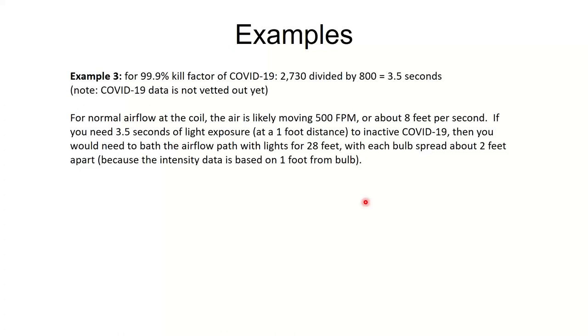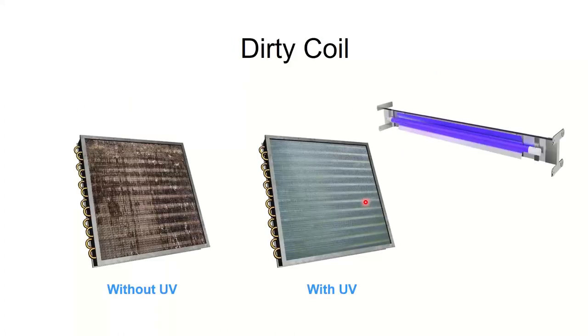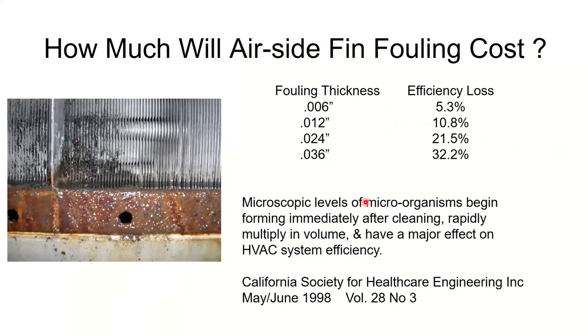but most of what you guys are doing is putting it by the evaporator coil, and it just doesn't do much for cleaning the air. It does a great job of cleaning coils, though. UV lights are excellent at cleaning coils because that's what they were designed for. And the main reason is the coil doesn't move. It's stationary. So I have all the time in the world to shine on it. I don't even need a very bright bulb. I just need more time. If I put in a wimpy bulb, 600, fine. I just need a few more minutes than I would with an 800 bulb because the coil's not going to move and go anywhere. So keeping coils clean, that's their primary job in life.